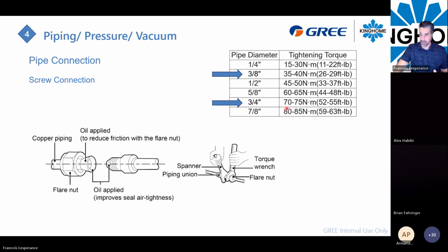You can set your torque wrench in Newton-meters, and you can measure the torque for your 3/8 somewhere between 35 to 40 Newton, or for a 3/4 somewhere between 70 to 75 Newton. Always use a second wrench or a spanner to hold the pipe and the valve correctly, and then with the torque wrench, you apply the right amount of pressure.